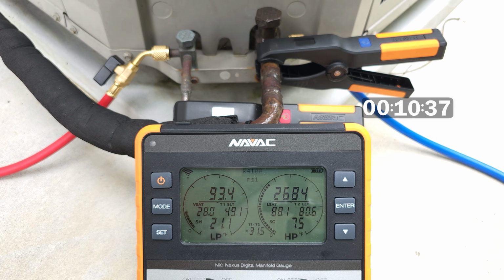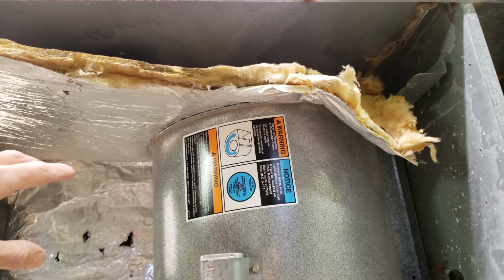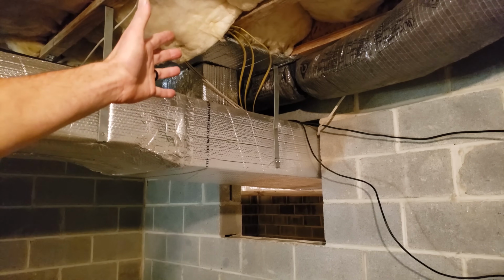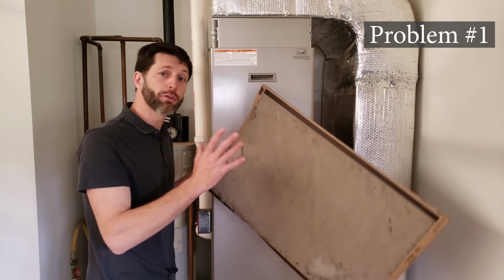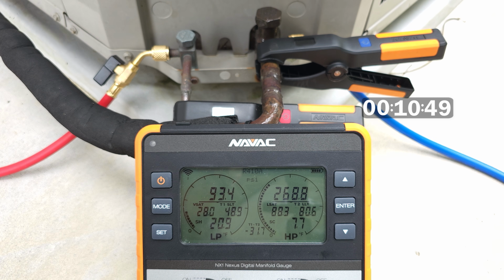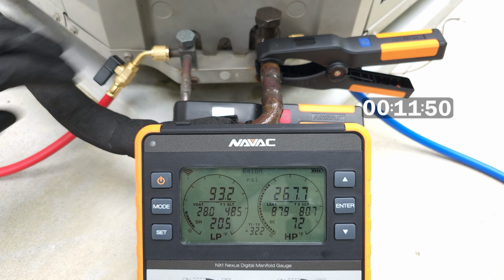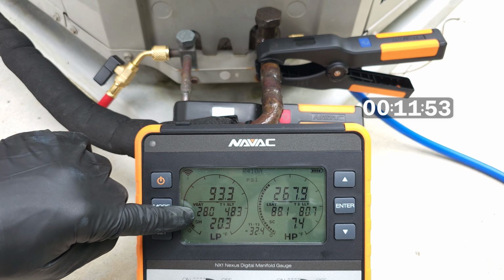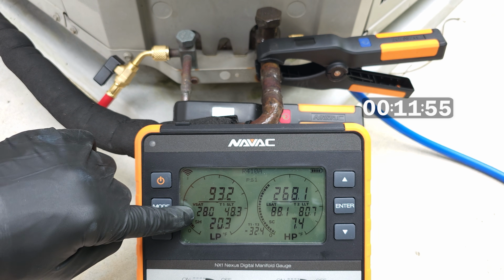We have to be able to adjust the airflow or find out if there's a clog in the ductwork, like the ductwork fell apart, the ductwork's undersized, maybe it's just as simple as a clogged filter. So it's airflow before charging. Always measure the airflow because that has to do with the energy transfer of the system just as much as the refrigerant charge. What I'm going to do at this point is pull this outdoor disconnect in order to shut this outdoor unit off. I'm going to allow the indoor coil to thaw out, and then we're going to be measuring the airflow at the indoor unit.